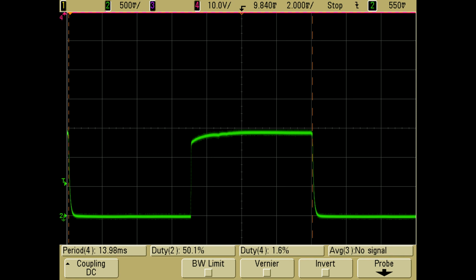As you can see here, channel 2 is the upstream waveform before it is amplified and sent to the pulse valve. Channel 2 is reporting a 50.1% duty cycle, and this is quite accurate. If you choose to use this waveform for adjustment, keep in mind that it is inverted in relation to the output waveform. A 40% duty cycle at the output waveform will correspond with a 60% duty cycle on this waveform.